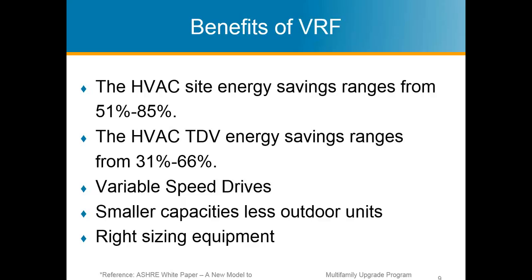So the results are climate-dependent. You know, this again is single family, not multifamily. When I model multifamily, I'm seeing mostly within the 20 to 30% range of your TDV savings. So it's not as high as what that white paper was saying, but they do have the capacity or the ability to reach high energy savings, which is basically the purpose of this slide. So by having variable speed drives on all those, being able to have smaller capacities on the indoor units and then fewer outdoor units.